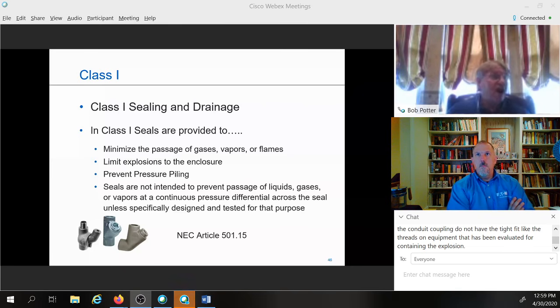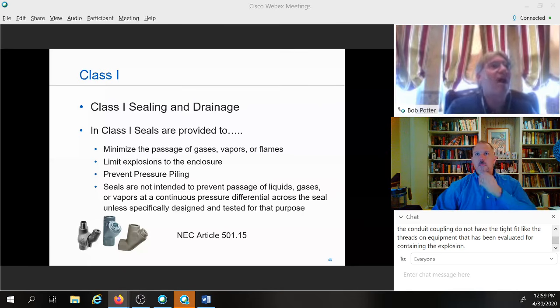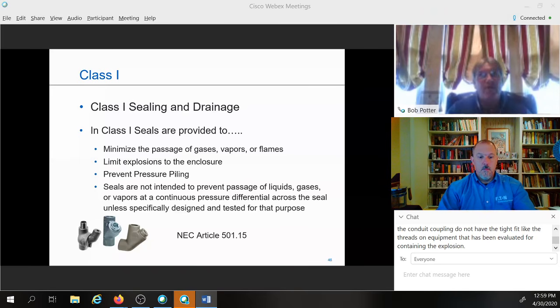Now, my normal rigid conduit and those particular couplings are certified. So in other words, you don't necessarily see, when you pick up a piece of rigid conduit, Class 1, Division 1 written on it, but that is an approved wiring method. And those couplings that you would see that go in conjunction with those are approved for a wiring method in Class 1, Division 1 and Class 1, Division 2. But the other fittings that you would put in there, whether it's a reducing bushing or a capped elbow or something along that line, are required to be certified.